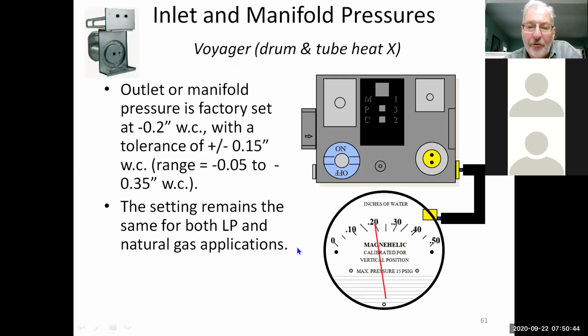Okay. So when you start these units, you're going to see your gauge probably drive down to about 2.5 to 3 inches negative. And then when the gas valve energizes, it's going to come back to a 0.2 negative, and that's where you want to be. That's your optimal position. You do have a range in there of 0.05 to 0.35. So if you want to set it up and clean it up a little bit, you can adjust that 0.05 to 0.35 negative if you need to. But typically, the 0.2 negative is where you want to be.